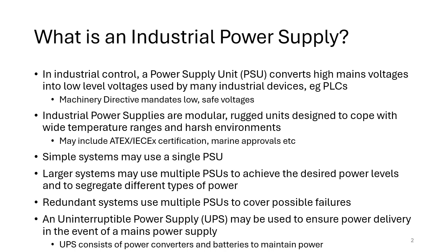Now, having said that, the incoming supply often isn't 24 volts DC. It would normally be a mains voltage, maybe 110 or 230 volts AC. So we do need the power supply to convert those incoming mains voltages into those low voltages. To do that, we use an industrial power supply, which is a modular, rugged unit designed to cope with wide temperature ranges and harsh environments.